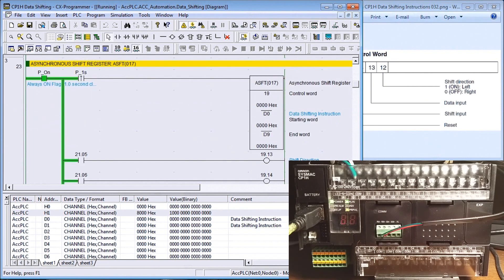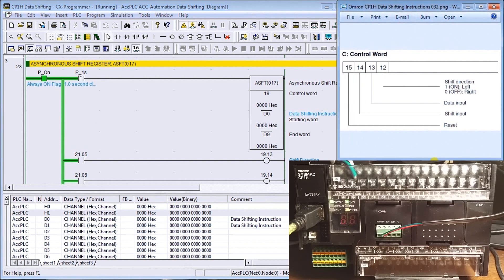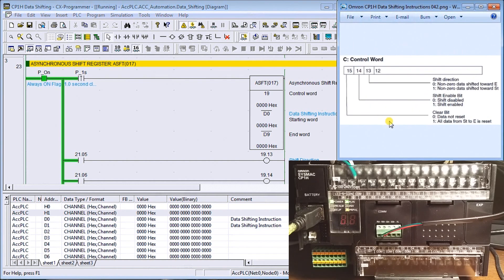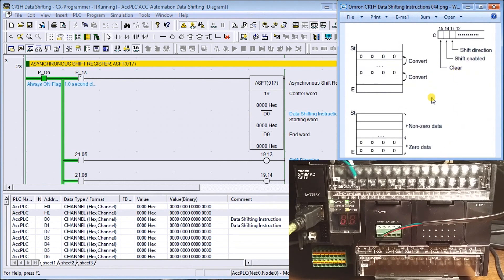Our next instruction is the asynchronous shift register. It also has a control word which enables the shift, clears the shift, shifts non-zero values, and sets shift direction — either towards the starting word or ending word. If the direction bit is on it shifts towards the starting word; if off, it shifts toward the ending word. Asynchronous means that if we have a zero it replaces that zero with another value and condenses everything down.